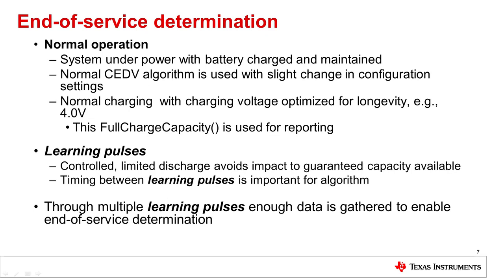During normal operation, the system will be powered with the battery plugged in, maintaining fairly a full charge. We have a CEDV gauging algorithm used in the part with some slight changes. Normally in a backup system, you may charge the battery to a voltage slightly below the maximum allowed — for example, in a lithium-ion system you may be allowed to charge at 4.2V but reduce that to 4.1 or 4.0V to give a longer life. The gauging algorithm calculates state of charge based on full charge capacity. As part of the end-of-service determination, which is a separate module from the gauging, we trigger very controlled learning pulses periodically with very limited depth, minimizing impact on the capacity available for the backup system.